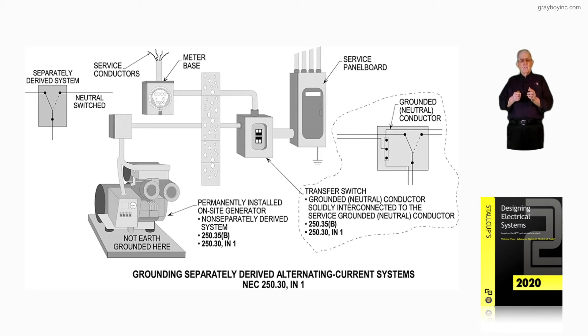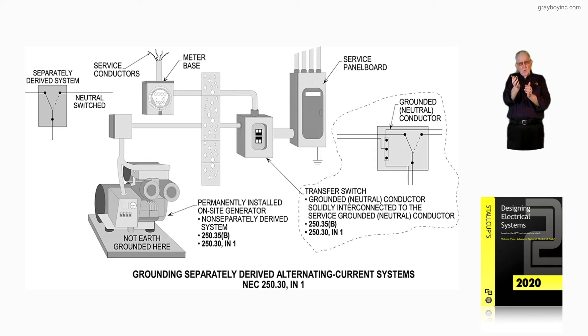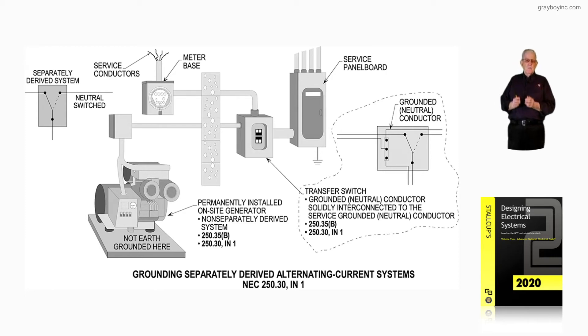All you and I as electricians, designers, or inspectors have to remember is: do they switch the grounded conductor with the ungrounded conductors? If the answer is yes, then informational note 1 to 250.30 says you ground the generator. But if they do not switch that grounded conductor and it ties into a bar that is grounded to the service ground and back to the utility ground, then you don't ground the generator. The generator is considered grounded through the service equipment ground according to informational note 1.